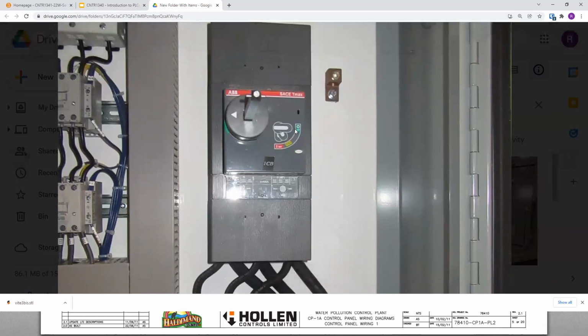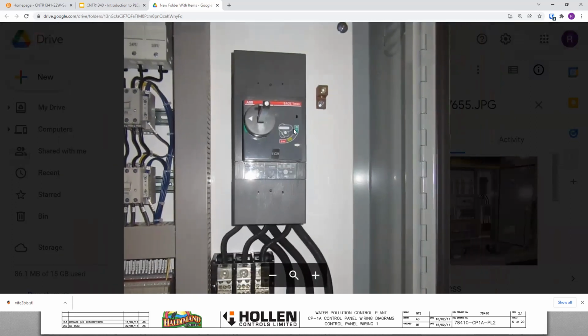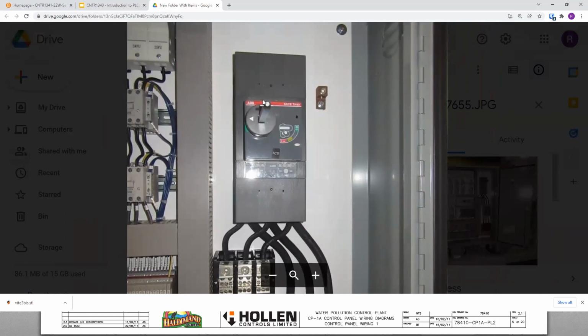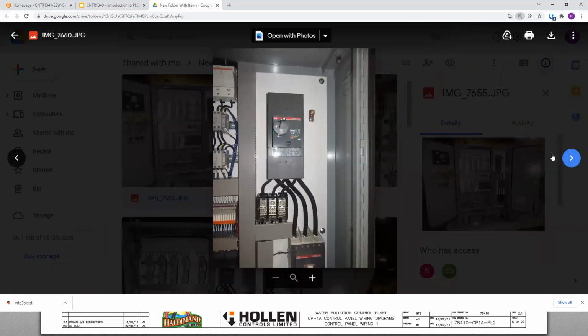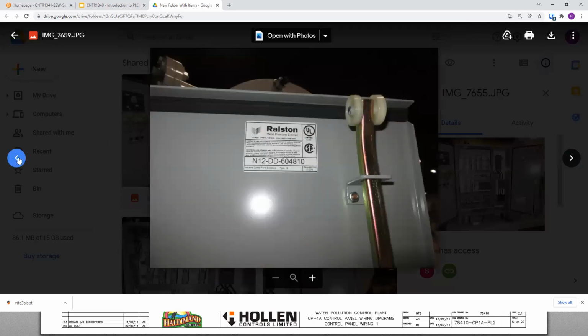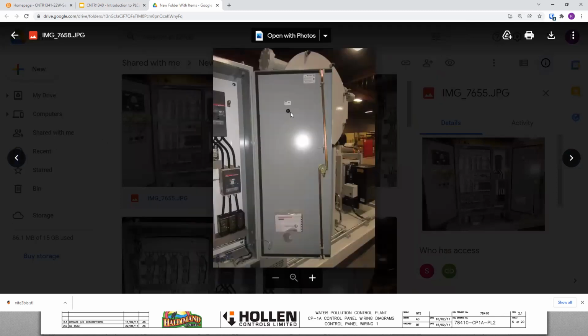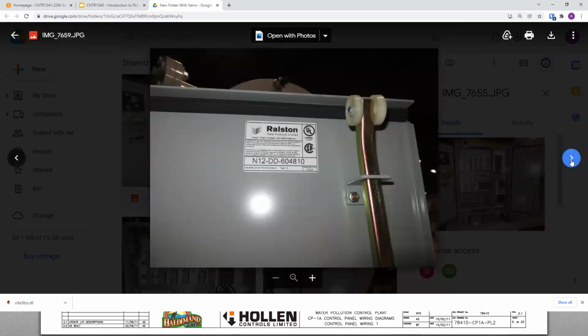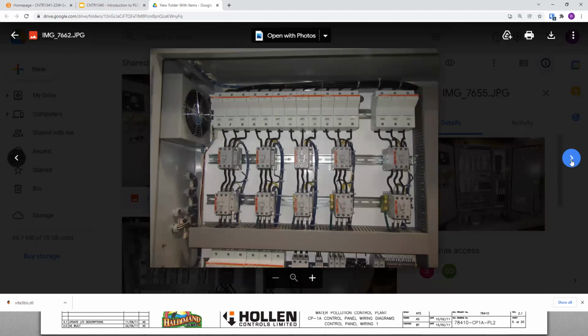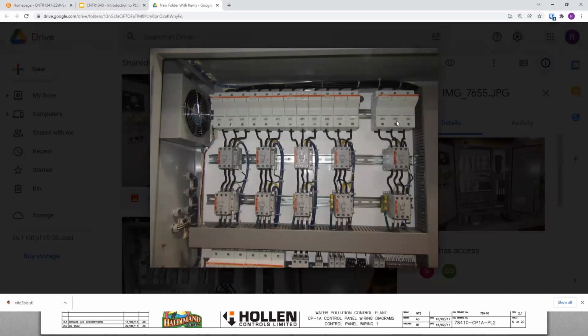So yeah, this is just a main breaker. This is going to be old hat for the electricians, but this type of breaker will actually reach through. This is a remote arm kit that will connect through to that hole. And if he has a photo of the front of the panel, there's actually going to be a rotary switch to turn on and off the main power feed to the panel. These up here, I think you can see my mouse, are going to be your fuse blocks.